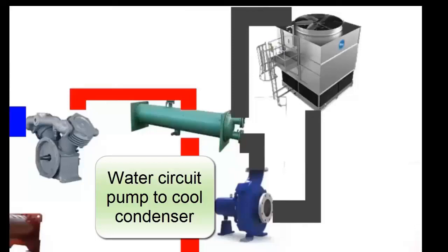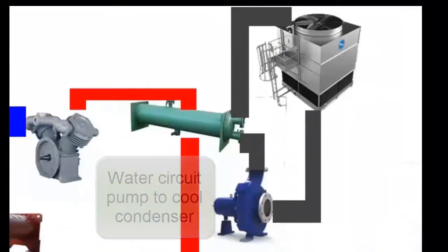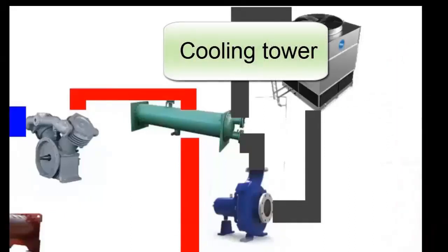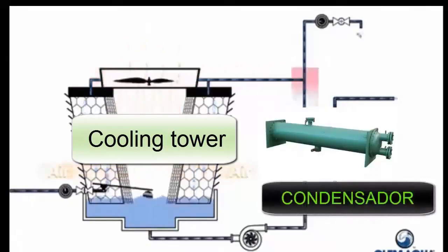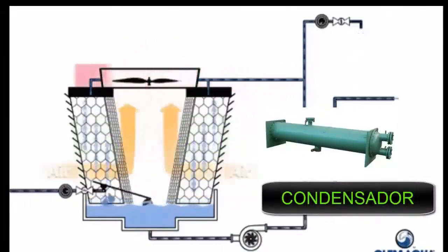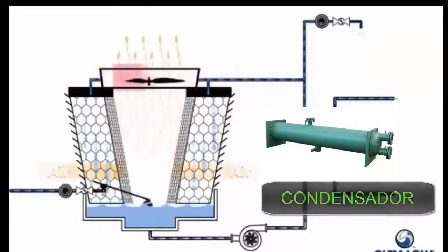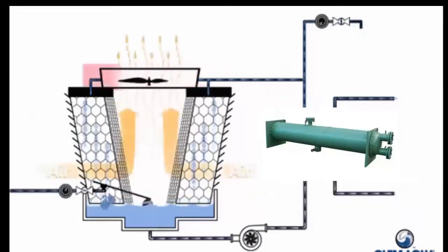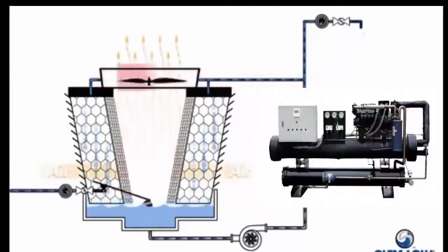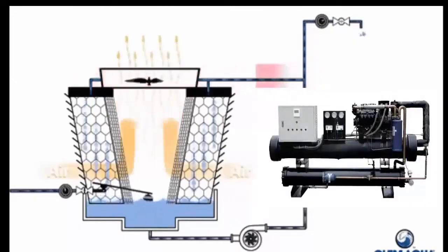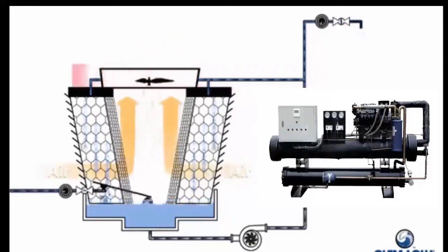What this new circuit does is collect heat at the refrigerant condenser, then send it through the system to what we call a cooling tower. In the cooling tower, the water arrives with the heat collected in the condenser and we cool it with fans — another heat exchange process between the water and the environment. The main advantage of this type of cooling is that the water will always have the wet bulb temperature while the air will always have the dry bulb temperature.